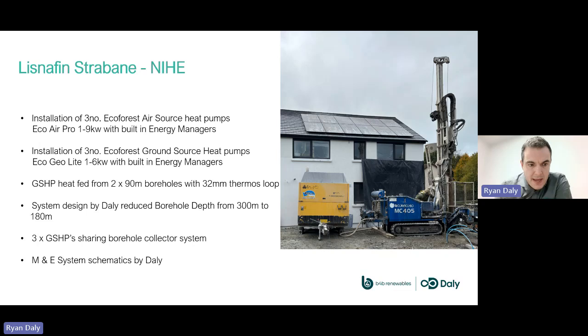The heat source for the ground source heat pump is 2 90-meter boreholes with 32 mm pipe in each borehole. We actually reduced the borehole depth, which the consultant had on his spec. He had it at 300 meters, but when we did our own heating calculations, we lowered that down to 180 meters, and so far so good. The temperature coming in when I was there on site recently was around 6.5, 7 degrees. So we're getting good temperatures from the borehole. The 3 ground source heat pumps share the boreholes, so it's a mini heat network, I suppose. And it's all worked really well.